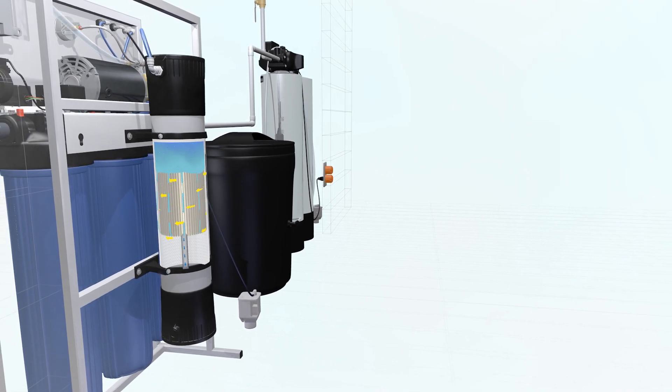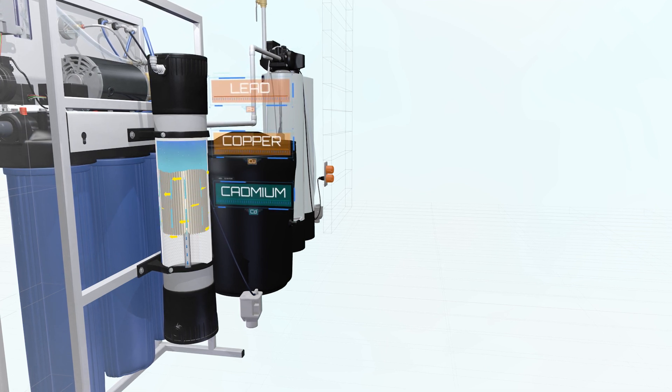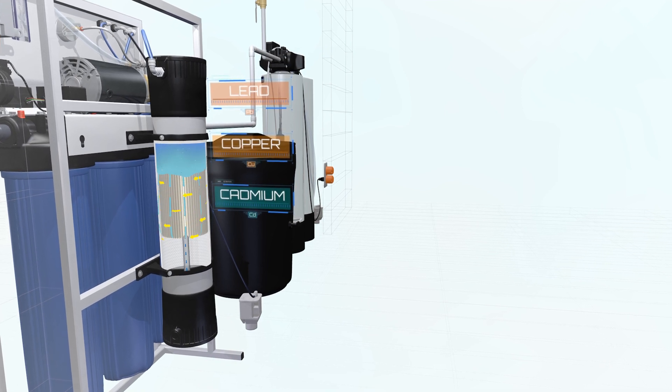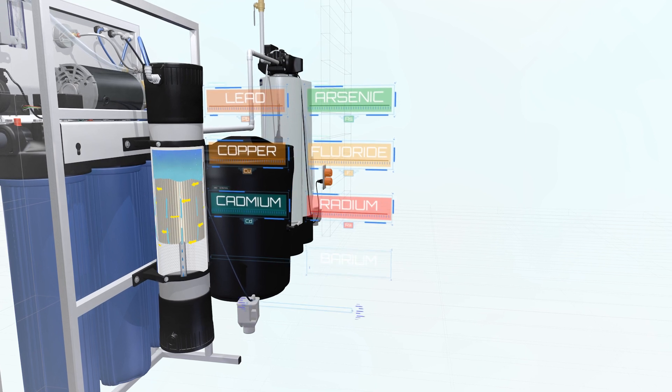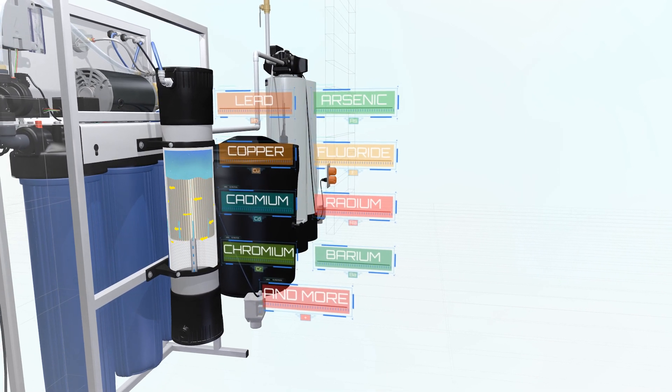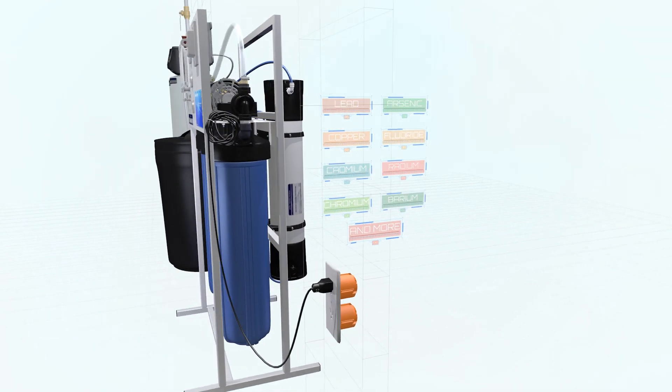Heavy metals like lead, copper, and cadmium are removed while purified water passes through the membrane. The RO process also removes salts, nitrate, arsenic, fluoride, radon, barium, and more. This highly efficient system can provide up to a 75% recovery rate.